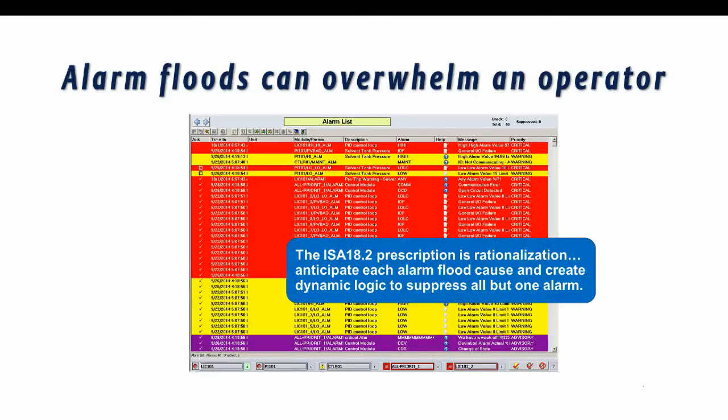The ISA 18.2 standard prescribes rationalization as a method to eliminate alarm floods. In this process, a team analyzes all of the potential conditions that may cause an alarm flood, determines how to identify the flood, and then creates logic to suppress all but one alarm.